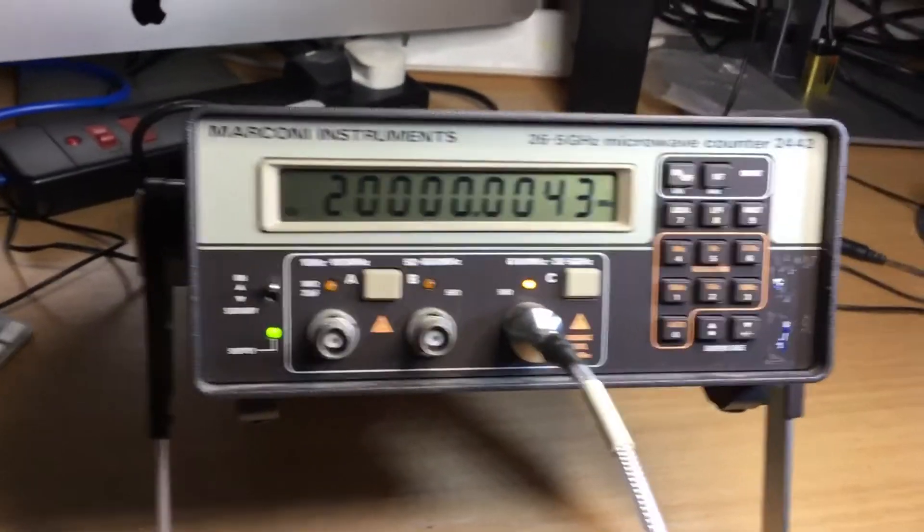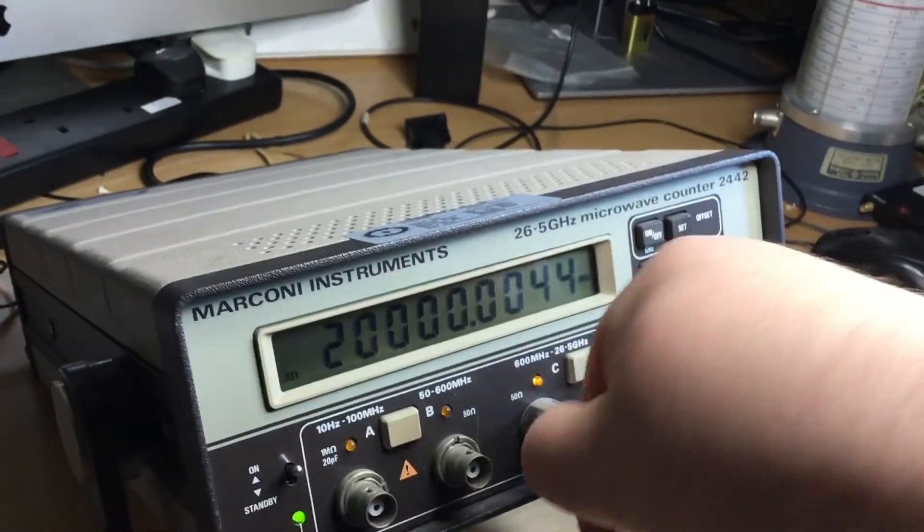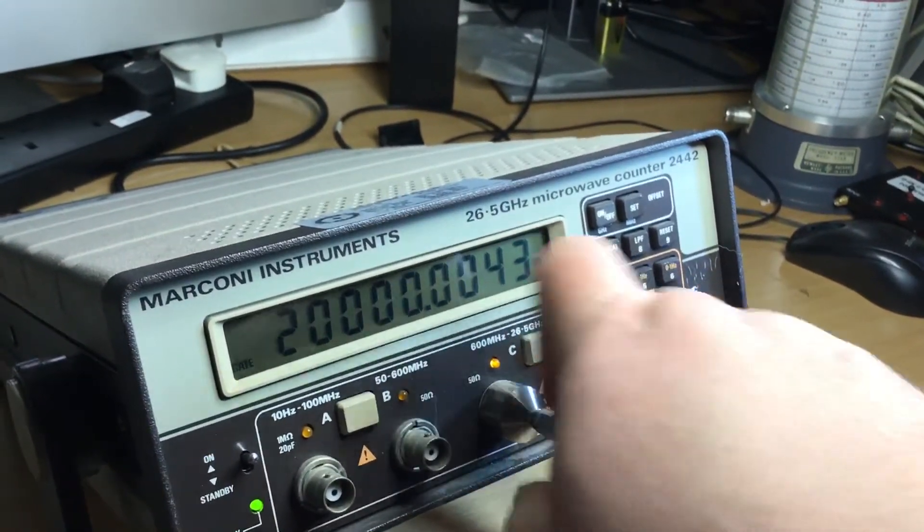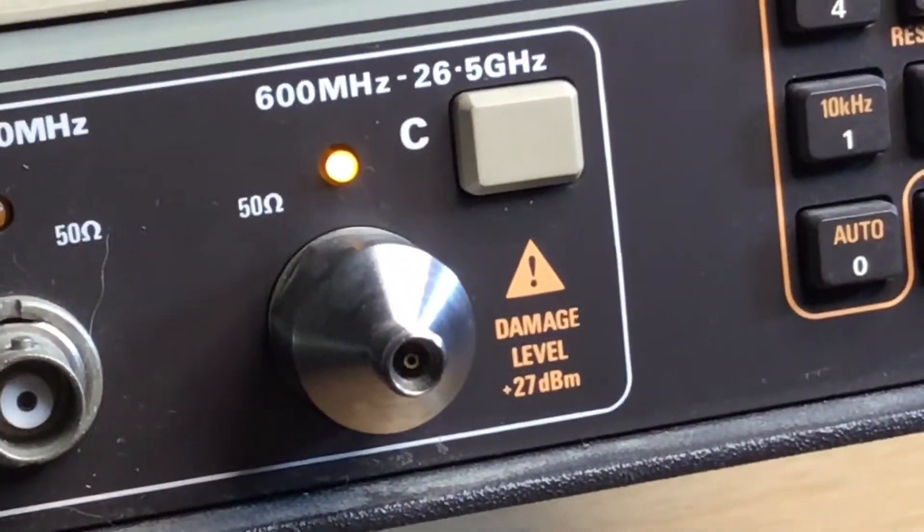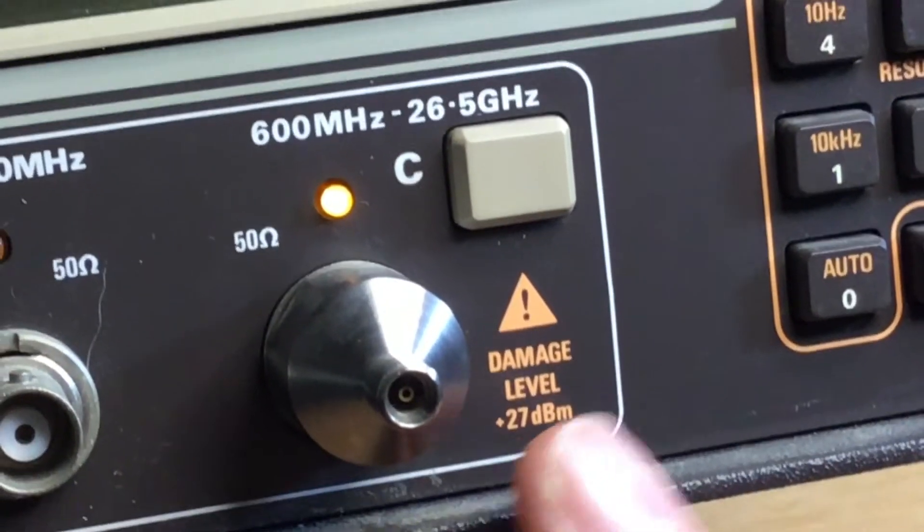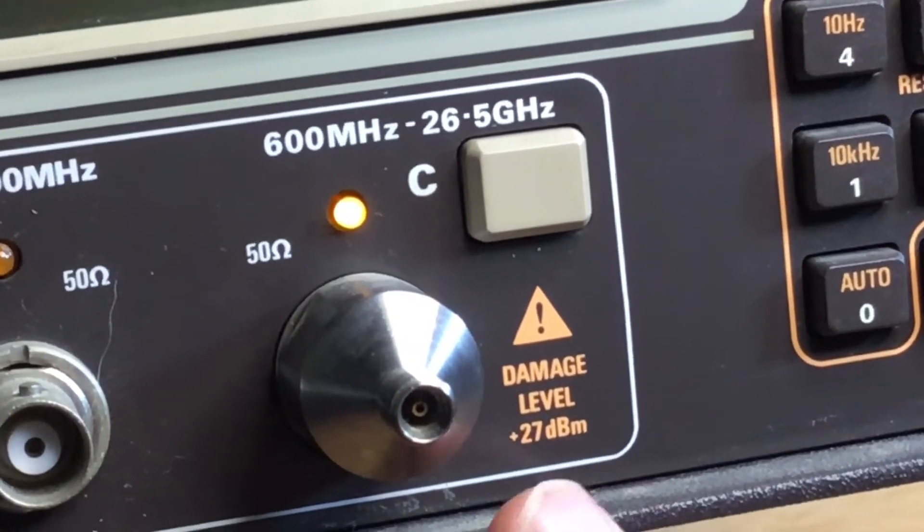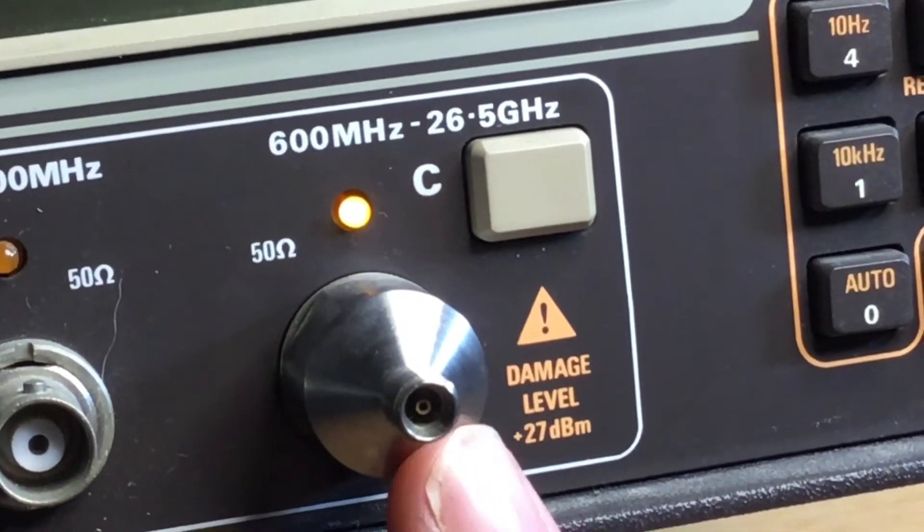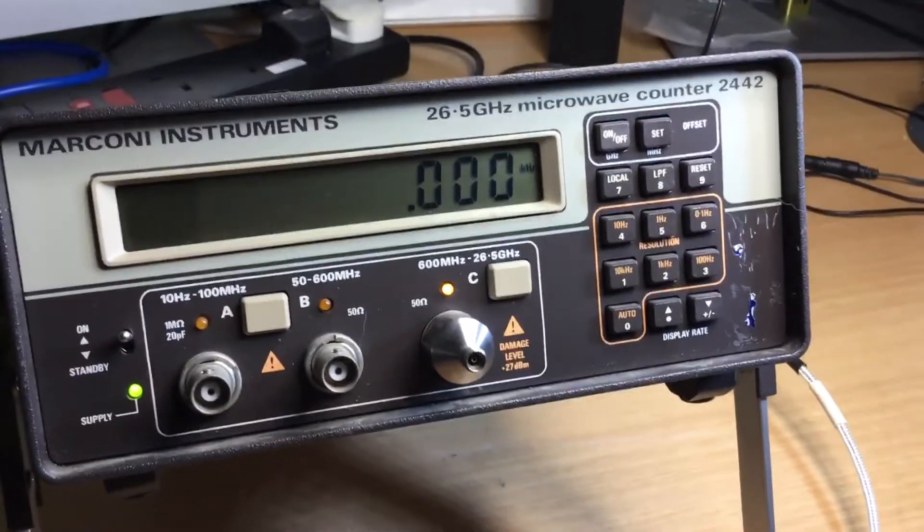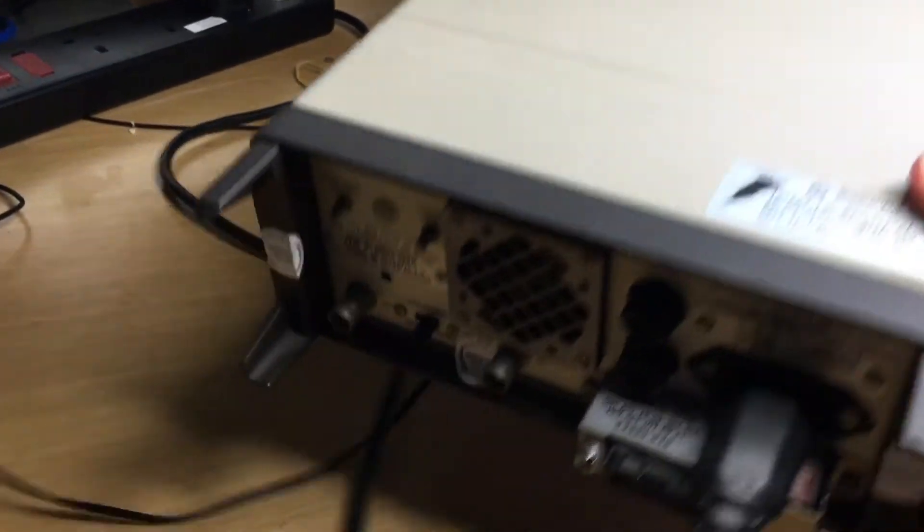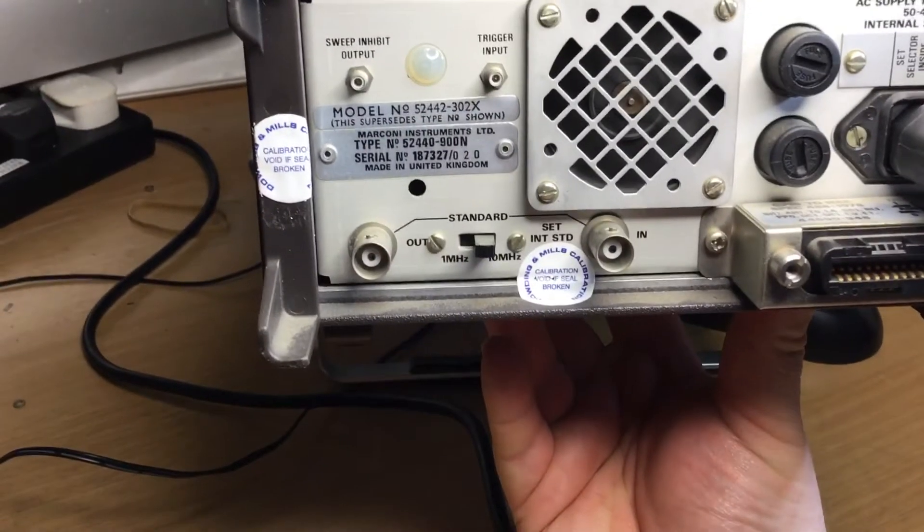It's just to show that the display isn't backlit. That's the only problem with these instruments from Marconi. A lot of them aren't backlit and can make it difficult to see them in bright conditions. So on the rear of the unit, if you just turn it around and disconnect this, I'll turn it round. That's the kind of port that we've got on the front. Again, always observe the damage level. Never connect these directly to transmitters, always via sniffers or some kind of coupler, resistive coupler. Never directly transmit into a frequency counter, otherwise you'll blow it, especially if you're transmitting high amounts of RF power over a watt.